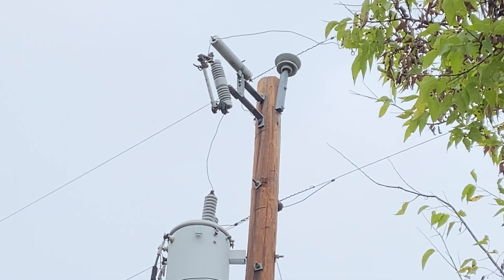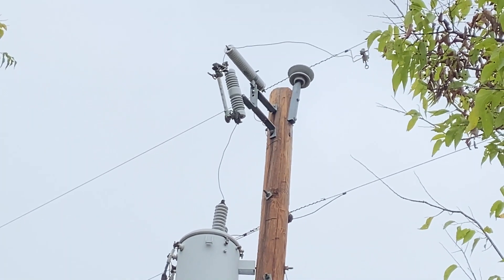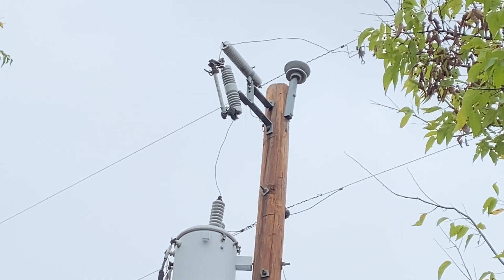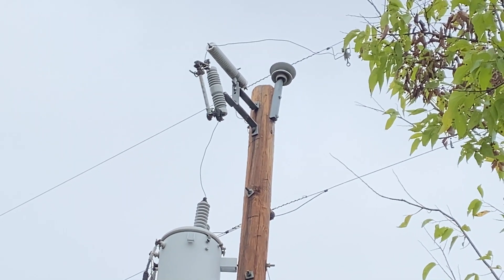This is the 18kV arrestor we're talking about. You can see it's got a hotline clamp bolted straight to the primary. We can't get it off with a shotgun, so we're going to cut it loose by hand.